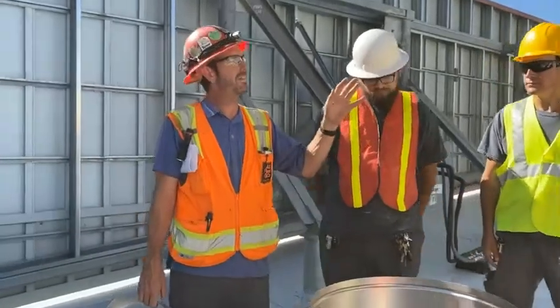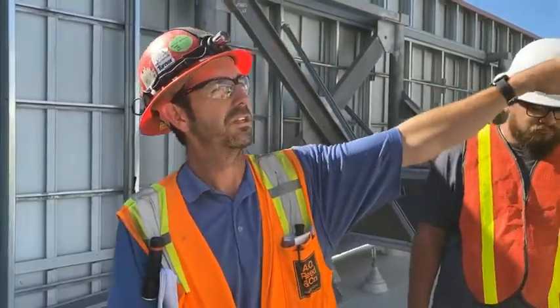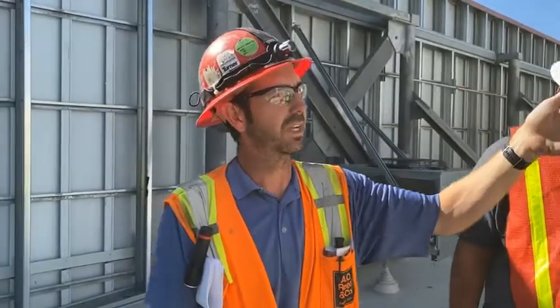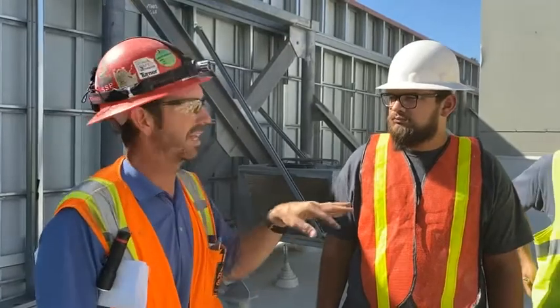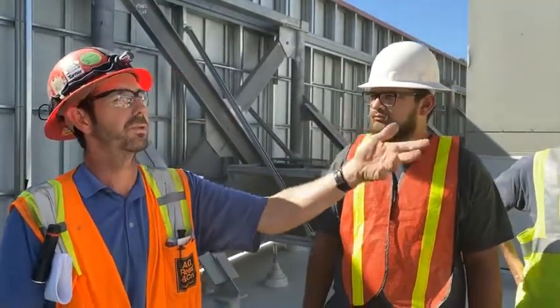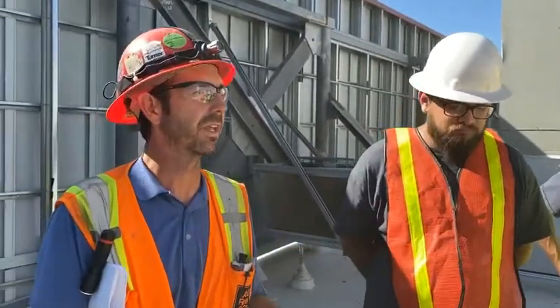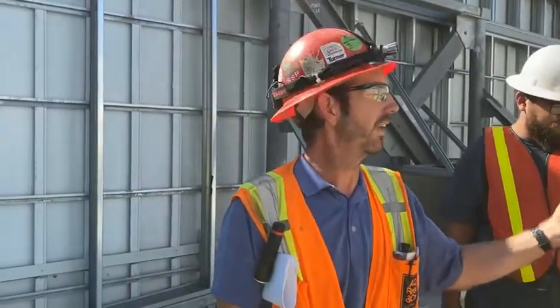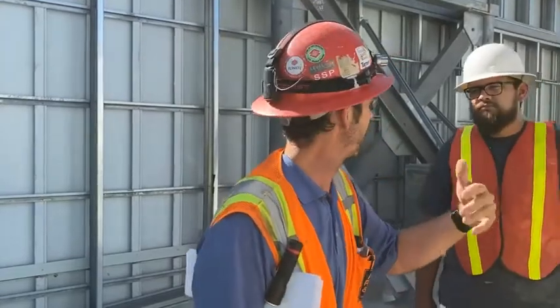Since we have the dedicated 100% outside air units, the fans, if they're running, will exhaust pressure out of the spaces. In the middle of the roof, there are huge pressure release louvers, okay? I don't think there's any on the sides, they're all in the middle. They relieve any pressure if the fan system's on, so you shouldn't feel the pressure ever coming out the front doors. If you felt any air pressure coming out the front doors, it could be that some of those louvers are plugged up, okay?